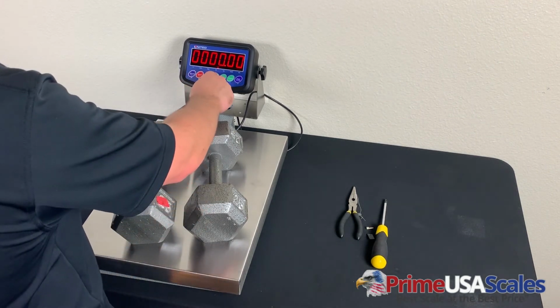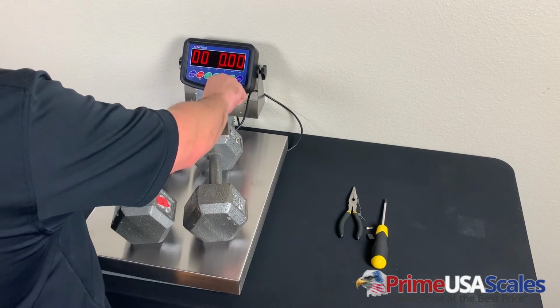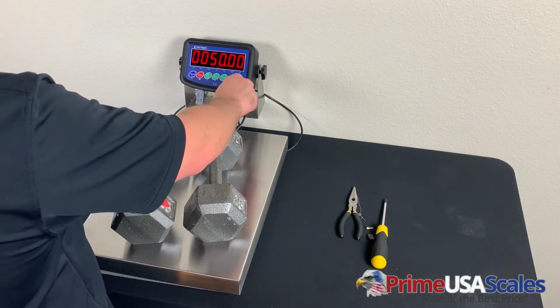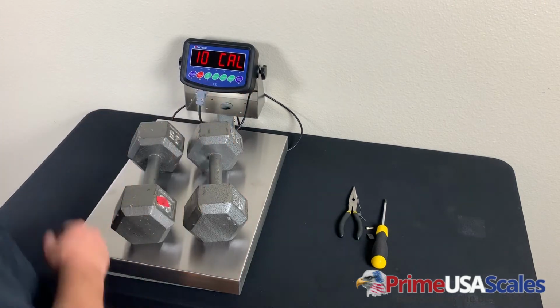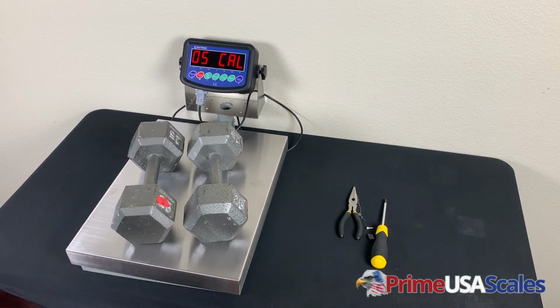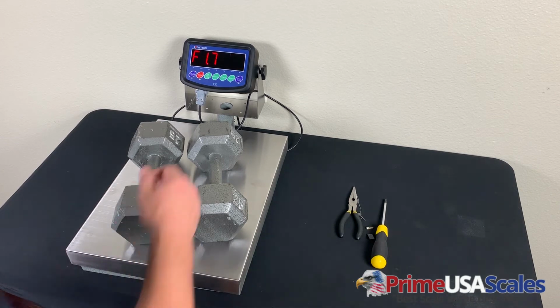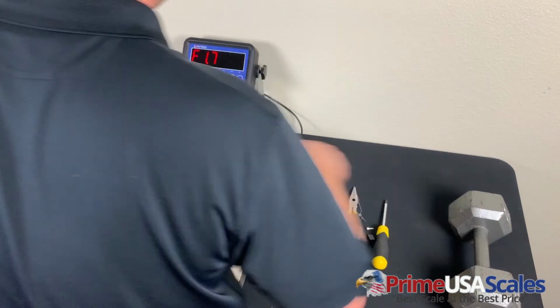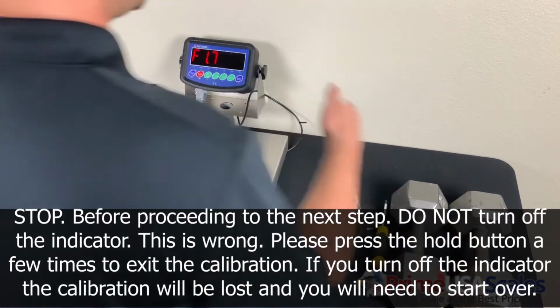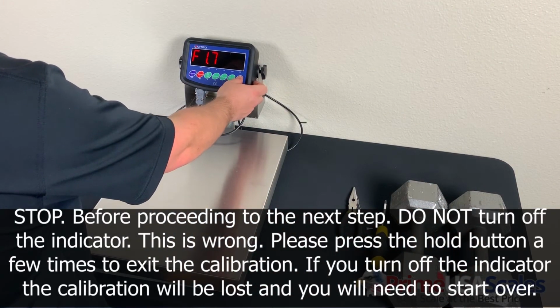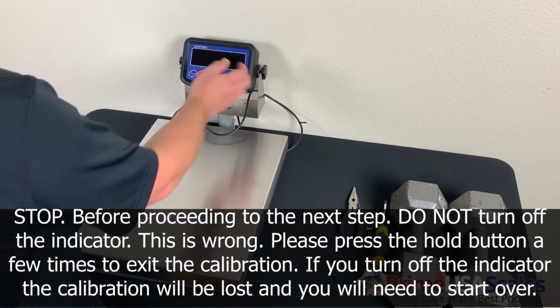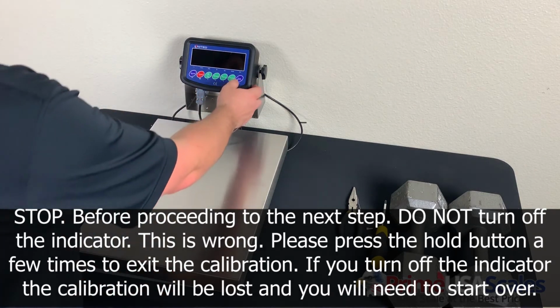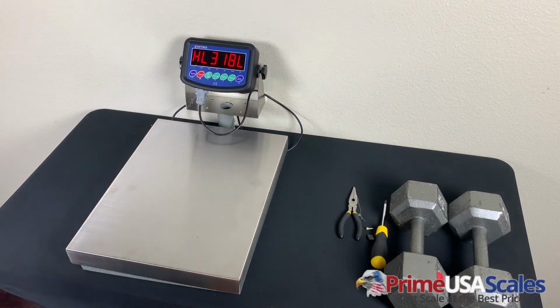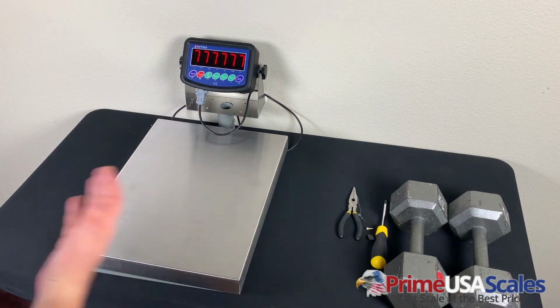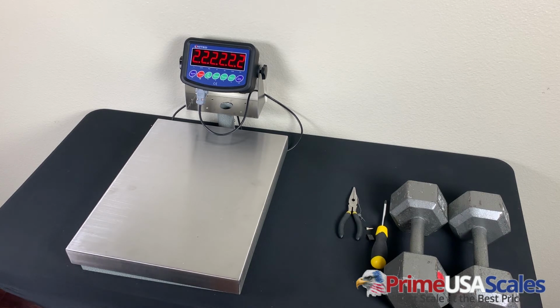So I'm going to toggle through and enter in 50 pounds. The scale will go through its countdown function again, and you want it to see 0 and it will hit end. After that is complete, we will take the weights off the scale and we will reset the indicator. We will shut it off by holding the button down and it will give you the off button. Then we're going to power it back on, let it go through the countdown sequence, and then we will test the scale to make sure that it's weighing accurately.